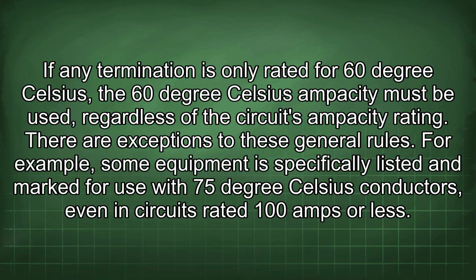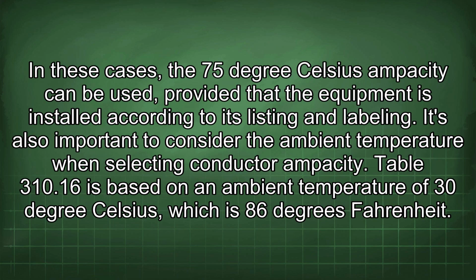If any termination is only rated for 60 degrees Celsius, the 60 degrees Celsius ampacity must be used, regardless of the circuit's ampacity rating. There are exceptions to these general rules. For example, some equipment is specifically listed and marked for use with 75 degrees Celsius conductors, even in circuits rated 100 amps or less. In these cases, the 75 degrees Celsius ampacity can be used, provided that the equipment is installed according to its listing and labeling.